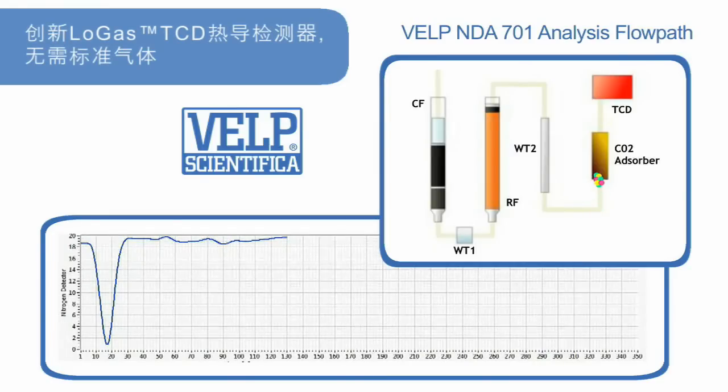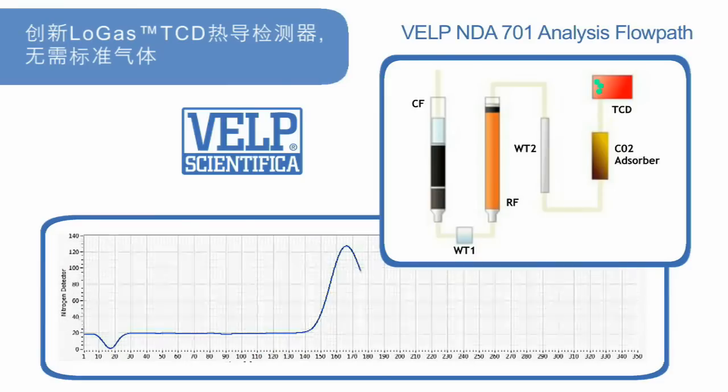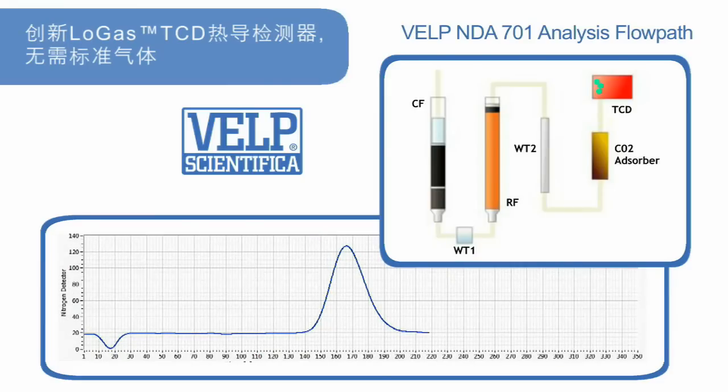At the end, the remaining elemental nitrogen is detected by the LoGas innovative TCD thermal conductivity detector without requiring a reference gas.